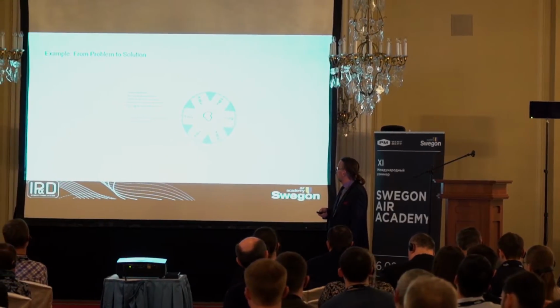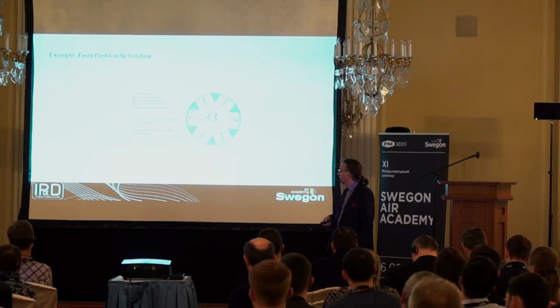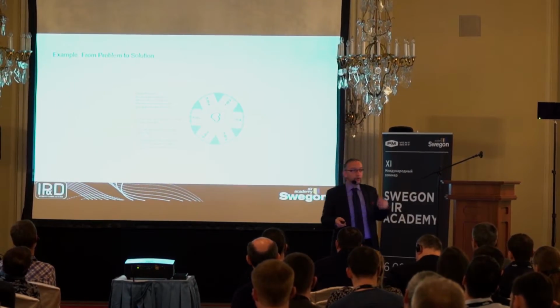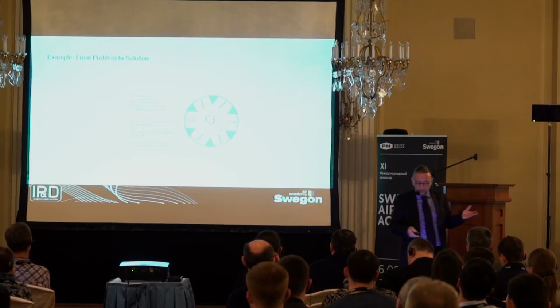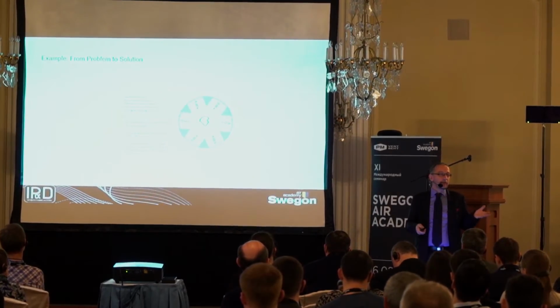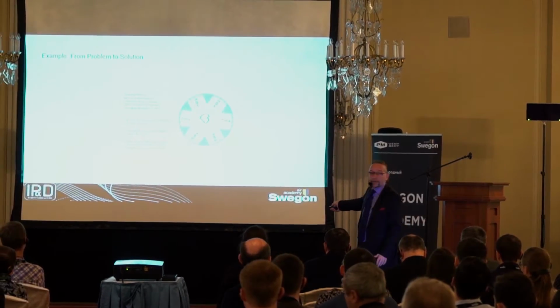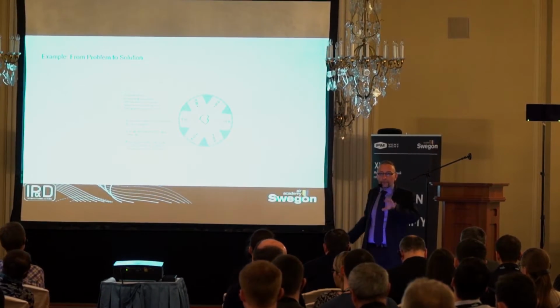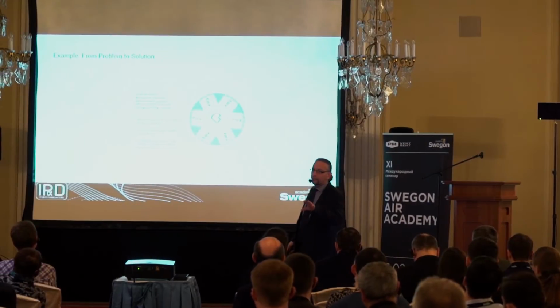So what happened: we increased the ventilation, we reduced the cost. We have more cost on the air handling units, of course, but we freed 1,000 square meters of rentable space. Do you know how much that is? That's 12 million euros of extra rental revenue over 15 years. So it doesn't matter if your equipment costs double or half, because that money is much more than your equipment ever costs. Don't be cheap on what you install—rather save cost around your products. That's much more clever in this situation.